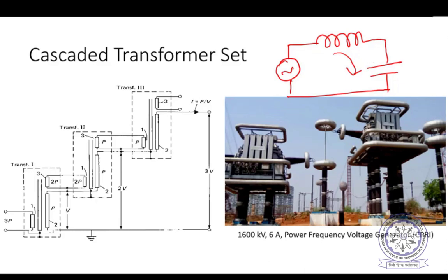So the voltage seen at the test object, this cable, will be different under resonant conditions. Very high voltages are expected, and that may cause breakdown. This actually happened in the field. Initially, cascading transformers were used for testing power equipment. When they were testing cables, premature failures were observed. After a lot of investigation, they found that resonance was occurring in the transformers. So this is one of the major disadvantages. You may be thinking the no load voltage is a very small value, but a very high value will be applied due to the resonance condition. So obviously the cable will break because the voltage is more than the normal voltage.